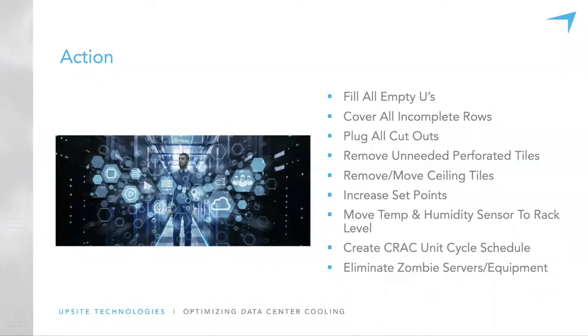I see a lot of people I work with, a lot of colos, say our PUE is 1.3, and that's what they advertise as a marketing tool. It may have very well been a PUE of 1.3 at that point, but I guarantee if you go back 10 or 15 minutes later, at a time with a different load, higher or lower, you're going to see a fluctuation in the PUE. The point that it can and will fluctuate is very valid.